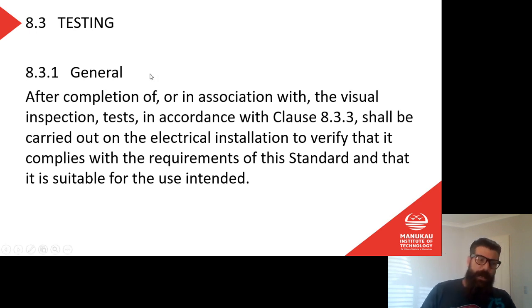We move on to section 8.3, which is the most important one. Testing. After completion of or in association with the visual inspections that we've just done, tests in accordance with 8.3.3 shall be carried out on the installation to verify it complies with the requirements of the standard and that it is suitable for the use intended.